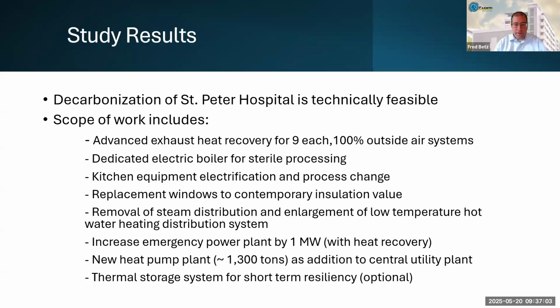So the results, we show that this is technically feasible. And here's a laundry list of things, some of which I talked about, of what would need to get done. Upgrading the heat recovery on 9 of the air handling units. A few of them, and this is something I kind of neglected to mention, are listed in the facility condition assessment as needing to be replaced anyway. So rather than replacing systems in kind, I would look at any system that you're working with at the moment. If it needs to be replaced, look how you can enhance that piece of equipment so it works towards your goal. We do need that dedicated electric boiler for sterile processing.